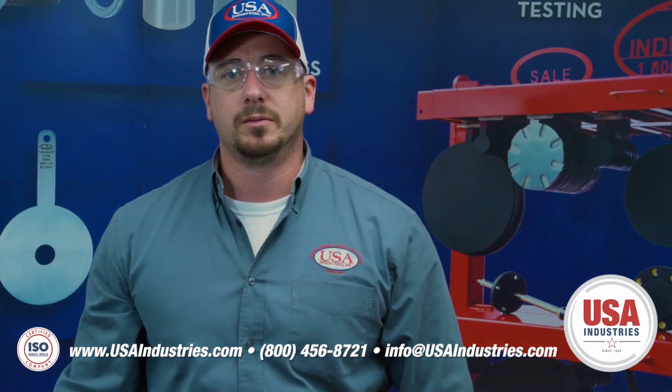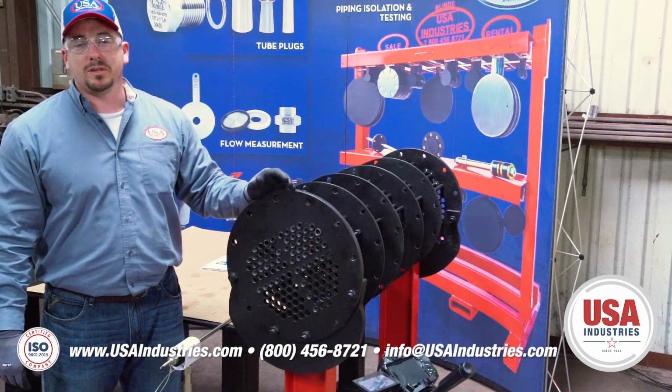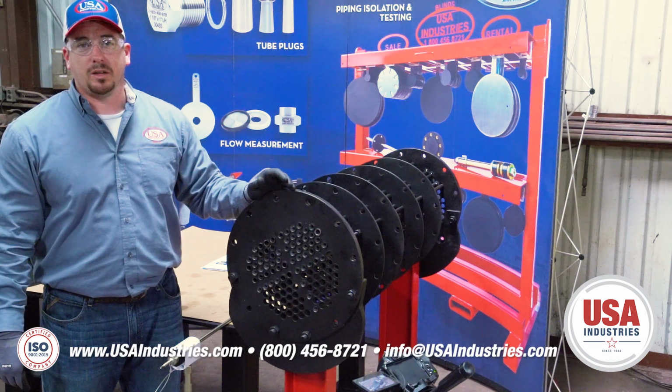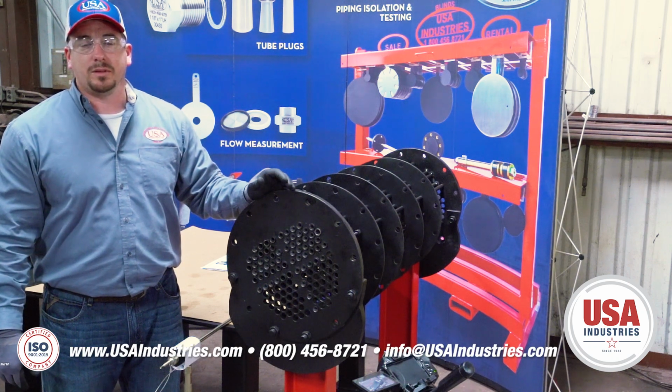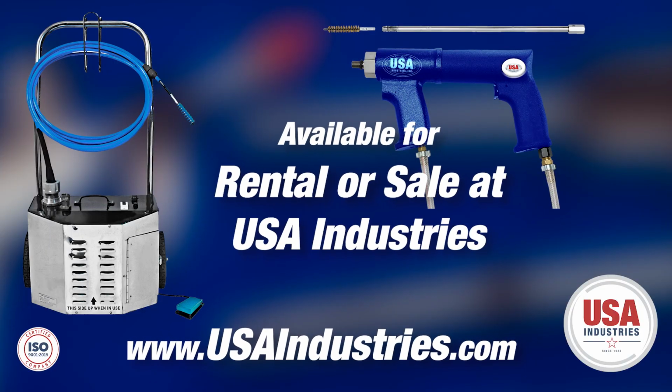to install a plug. First, I want to address the fact that we are not utilizing a brush kit like we did on the near-end installation. The reason being is you cannot get the brush kit all the way down the ID of the tube to the back tube sheet. So you want to make sure those tubes are as clean as possible, whether you use a flex shaft cleaner or have them lance out.